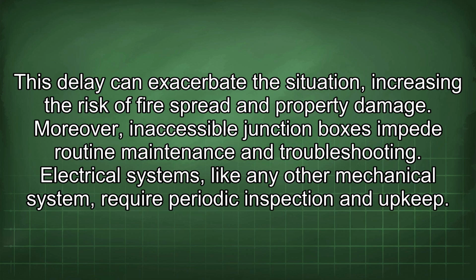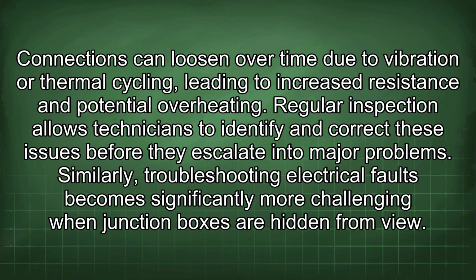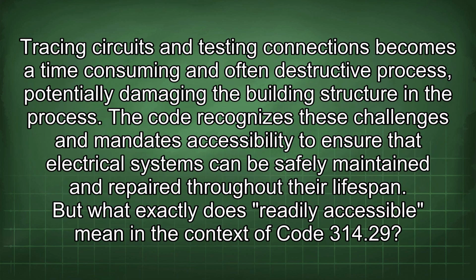Moreover, inaccessible junction boxes impede routine maintenance and troubleshooting. Electrical systems, like any other mechanical system, require periodic inspection and upkeep. Connections can loosen over time due to vibration or thermal cycling, leading to increased resistance and potential overheating. Regular inspection allows technicians to identify and correct these issues before they escalate into major problems. Similarly, troubleshooting electrical faults becomes significantly more challenging when junction boxes are hidden from view. Tracing circuits and testing connections becomes a time-consuming and often destructive process, potentially damaging the building structure in the process. The code recognizes these challenges and mandates accessibility to ensure that electrical systems can be safely maintained and repaired throughout their lifespan.